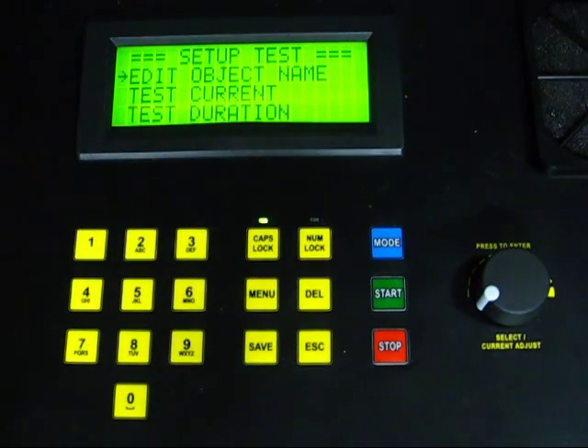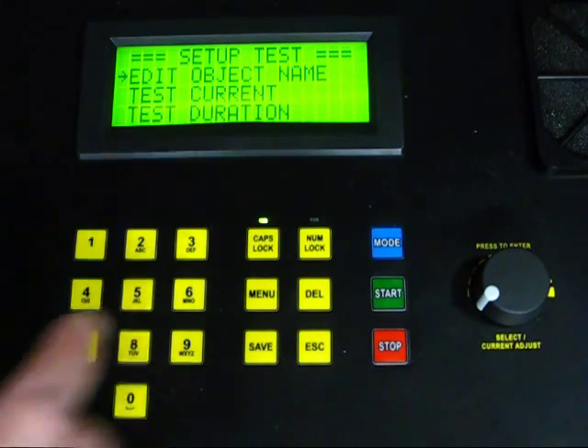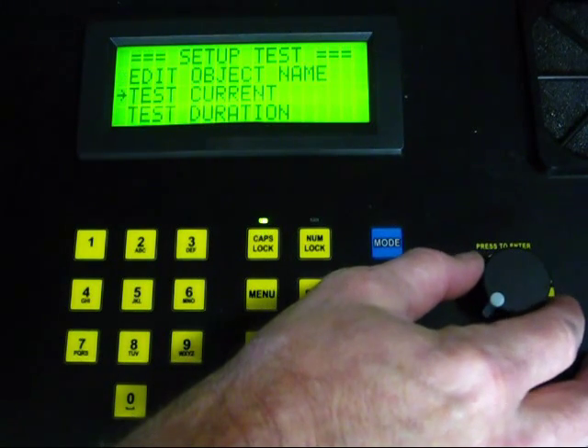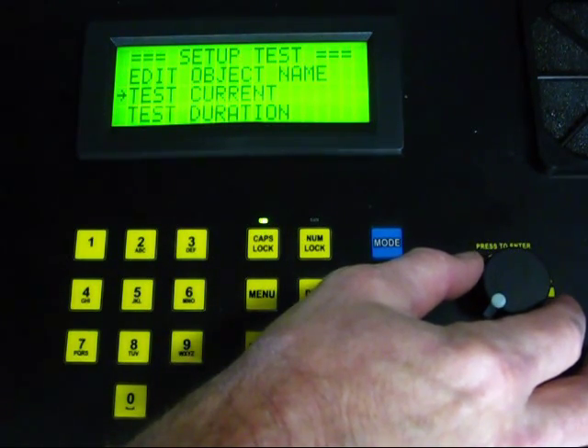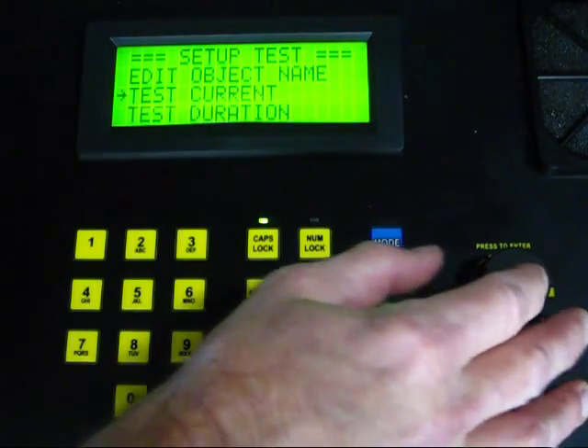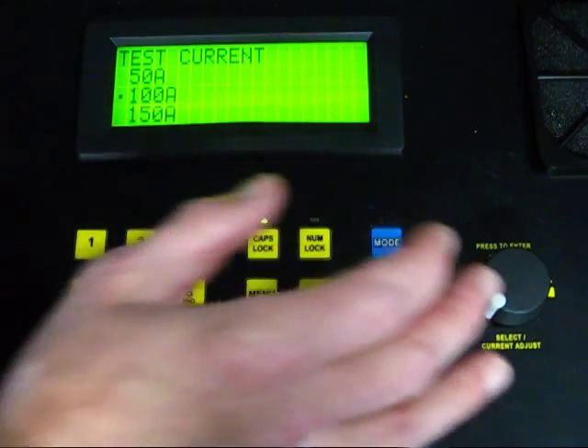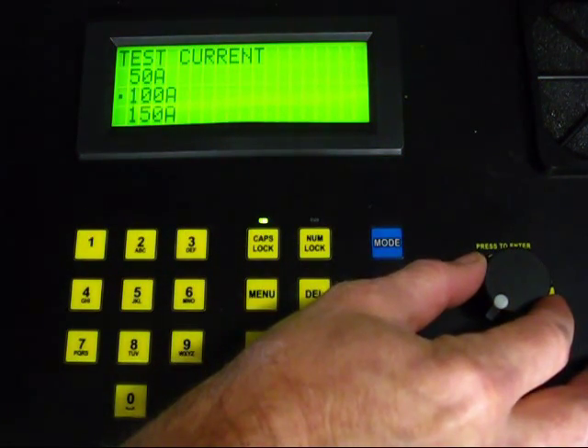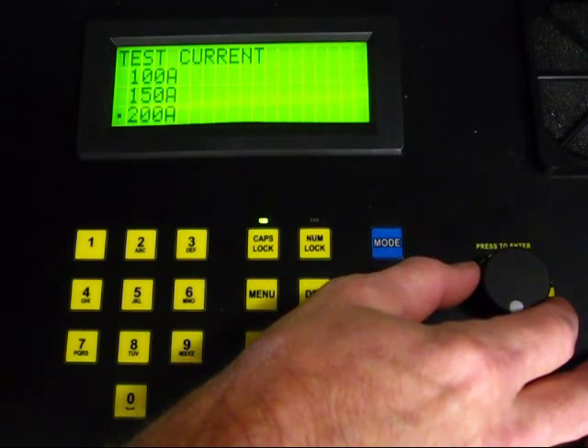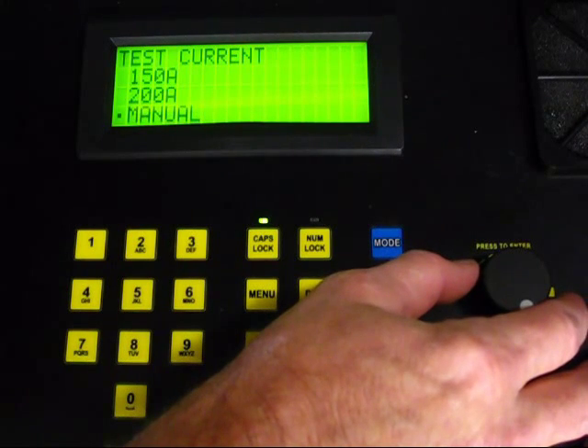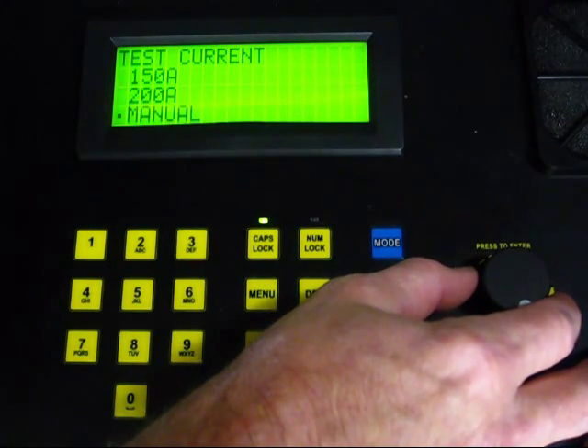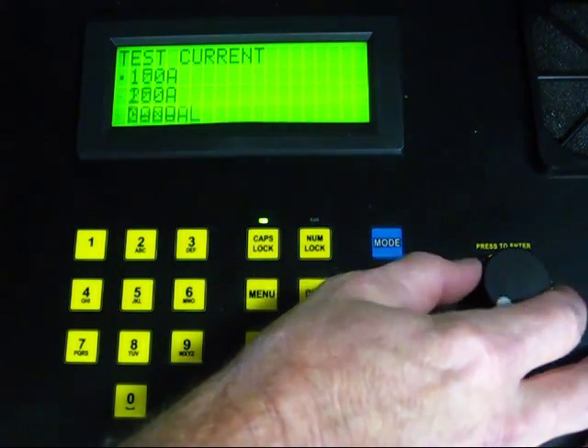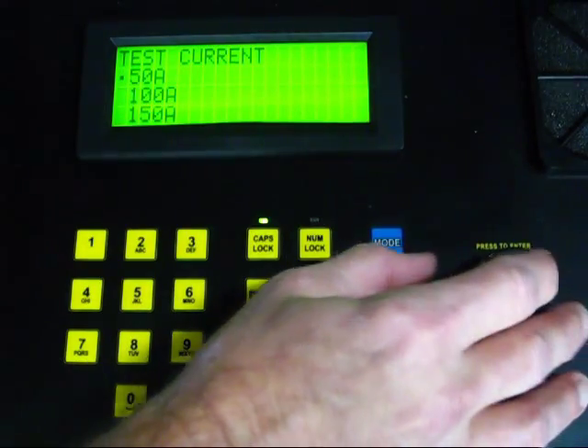Turn the rotary knob counterclockwise to move the selection arrow on the LCD screen down to the option Test Current. Press the rotary knob to display the Test Current menu. Turn the knob to select the current setting for the test. The menu offers four fixed current settings: 50, 100, 150, and 200 amps. You can also select the Manual option. This option allows you to control the amperage during the test by turning the rotary knob. In the manual mode, the current is limited to 100 amps. In our test, we will choose 50 amps.